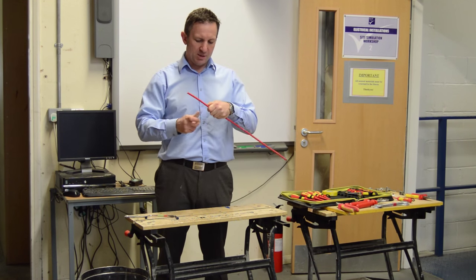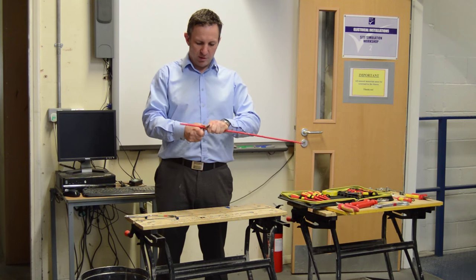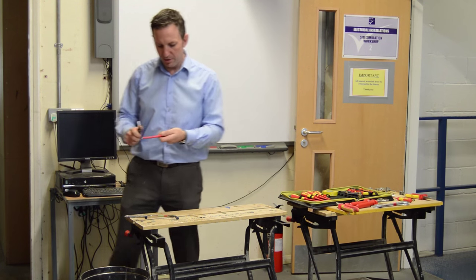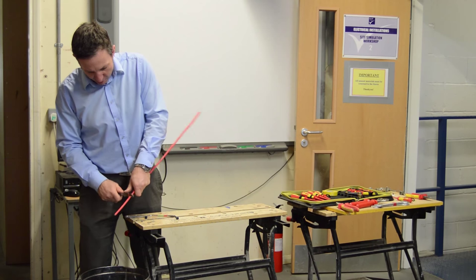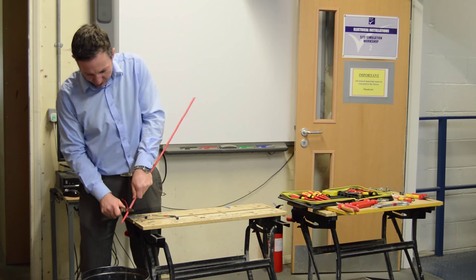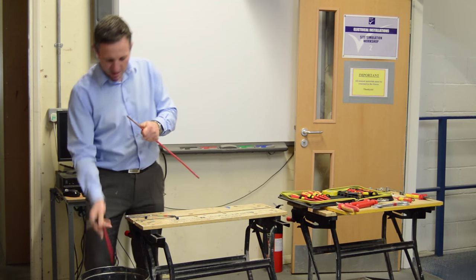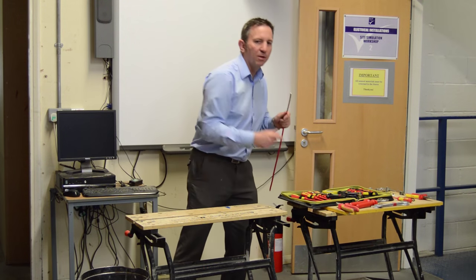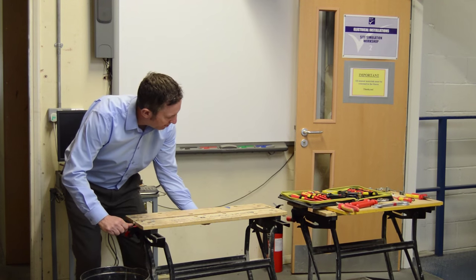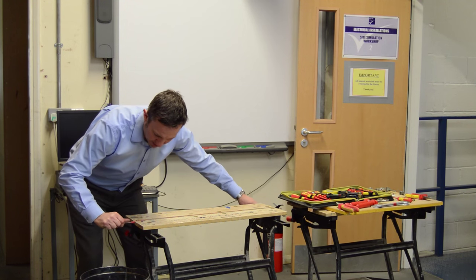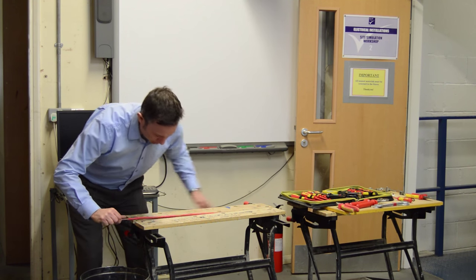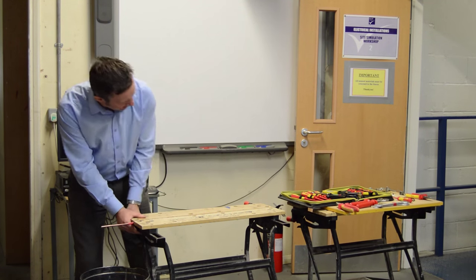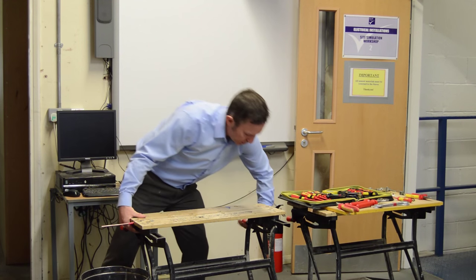Being as careful as always we're not cutting ourselves. Make sure we always use the cable for protection. We're going to ring round and then we're going to strip off the outer insulation. When we do that always make sure we're above a bin. That way we keep good housekeeping and save serious time at the end of the day. So what we're going to do is strip off the outer sheath. Once that's done the most important part is to get our cable into our workmate and keep it secure. We're going to put our cable in, keep it nice and secure. Tighten up our workmate. Stop the outer sheath from spinning.